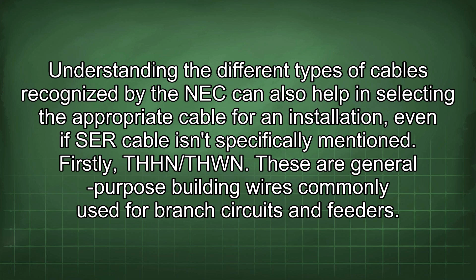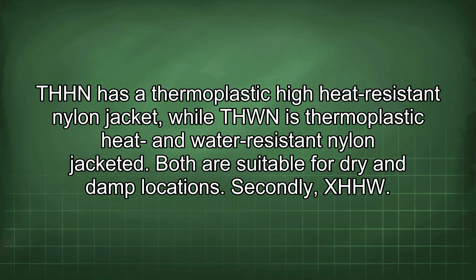Firstly, THHN/THWN. These are general-purpose building wires commonly used for branch circuits and feeders. THHN has a thermoplastic high heat-resistant nylon jacket, while THWN is thermoplastic heat and water-resistant nylon jacketed. Both are suitable for dry and damp locations. Secondly, XHHW. This is a cross-linked polyethylene high heat and water-resistant wire, suitable for wet and dry locations.